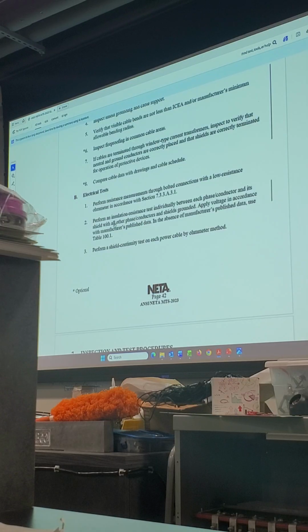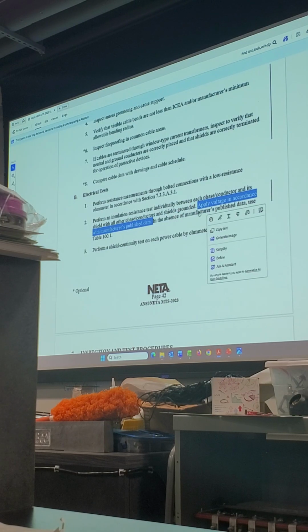Apply voltage in accordance with manufacturer's published data. This is what I mentioned very early on, and you're going to see this a lot in pretty much all the sections that say NETA will defer to the original manufacturer. Again, they are expected to be the utmost authority on their own equipment. But in the absence of that, where we find ourselves in this class, that's when we use 100.1.